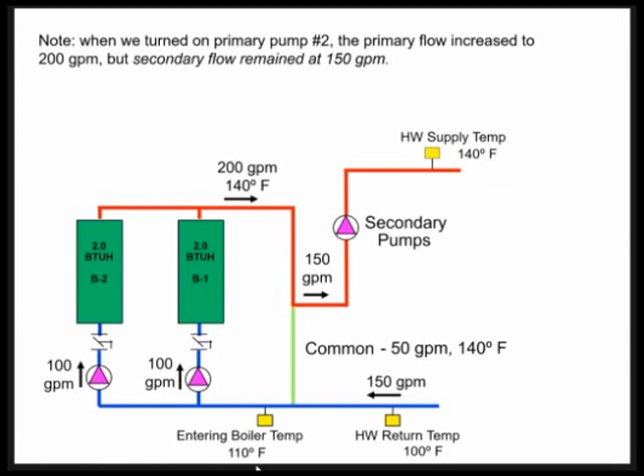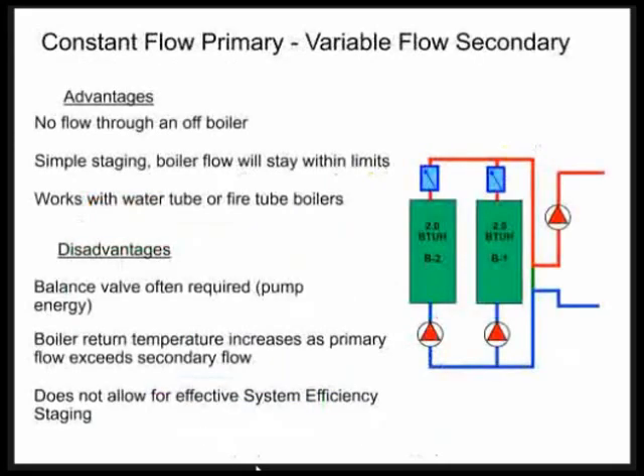Remember, when we turn on primary pump number two, the primary flow increased to 200 GPM. And the secondary flow remained at 150. So there's some advantages and disadvantages of constant flow primary, variable flow secondary.